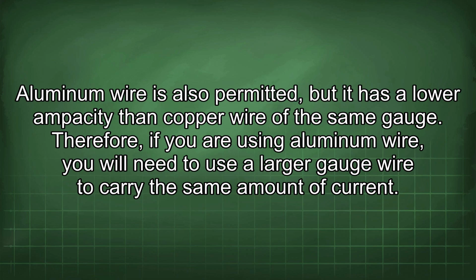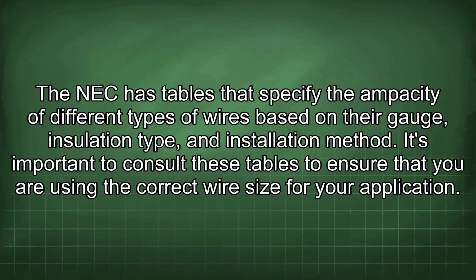Aluminum wire is also permitted, but it has a lower ampacity than copper wire of the same gauge. Therefore, if you are using aluminum wire, you will need to use a larger gauge wire to carry the same amount of current. The NEC has tables that specify the ampacity of different types of wires based on their gauge, insulation type, and installation method. It's important to consult these tables to ensure that you are using the correct wire size for your application.